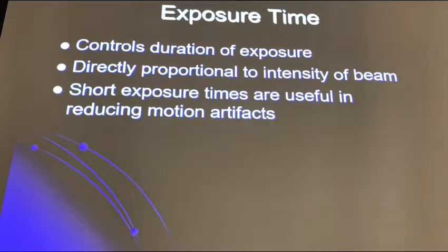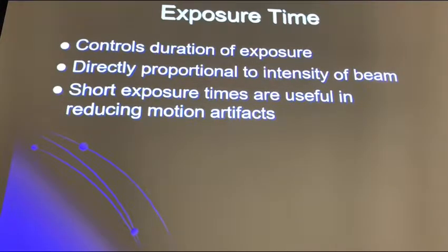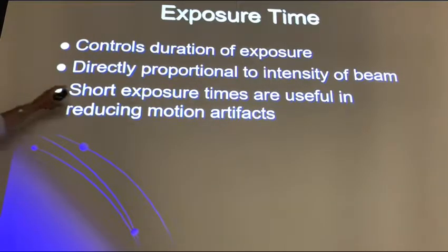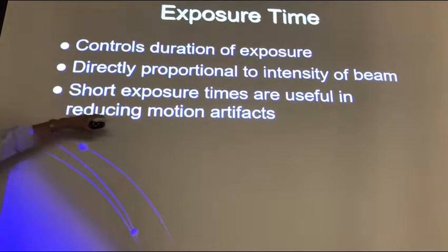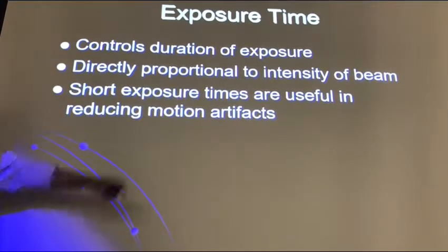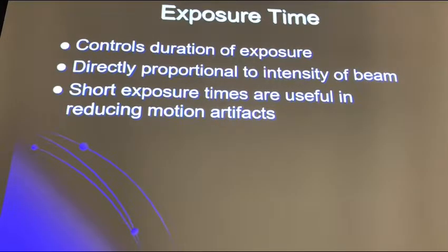Exposure time controls the duration of the exposure — for how long you allow the electrons in the electron cloud to flow from cathode to anode. It is directly proportional to the intensity of the beam. Short exposure times are useful for reducing motion artifacts — for example, when imaging a child or baby, it's recommended to use a high mA station and a very short time.